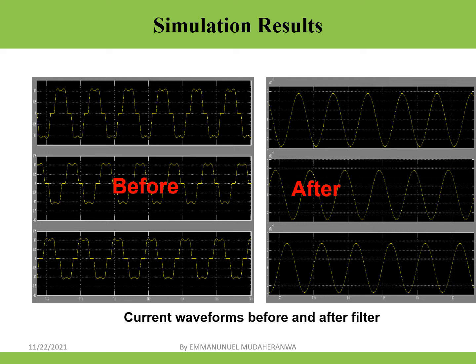As a result, you can see that before introducing the active power filter, we have a distorted current waveform for each phase — phase A, phase B, and phase C. After introducing the active power filter, as shown on the right side, the distorted waveform has changed into a complete sinusoidal waveform. All phases are completely filtered and the harmonics are eliminated.